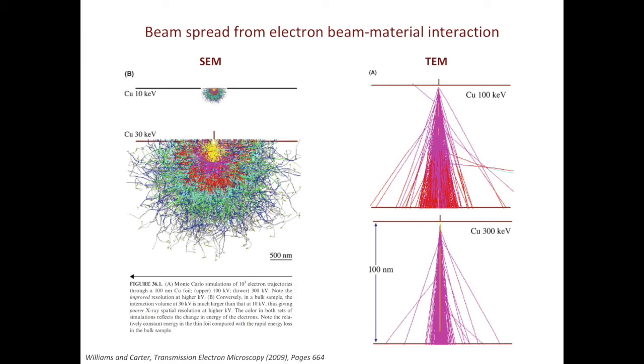To wrap up this slide, in SEM, if you increase the acceleration voltage of the electron beam, the interaction volume and the beam spread will increase. In TEM, due to the finite thickness of the specimen, if you increase the acceleration voltage of the beam, both the interaction volume and the beam spread will be reduced.